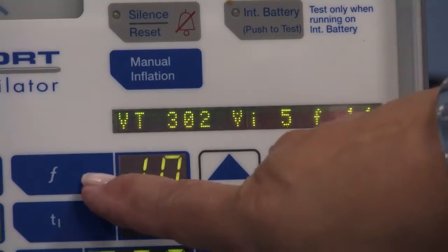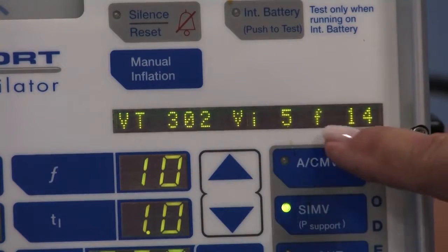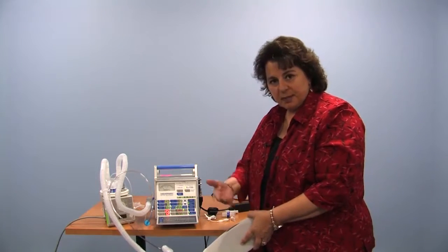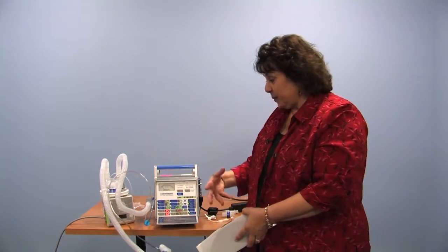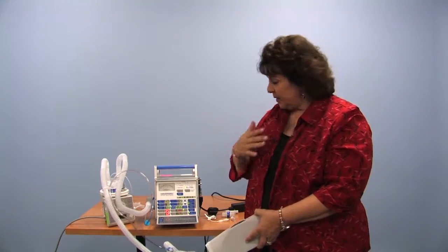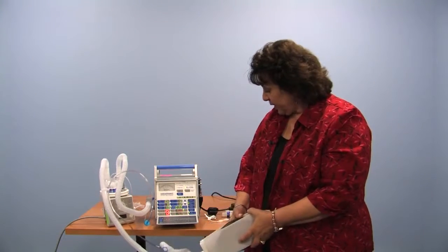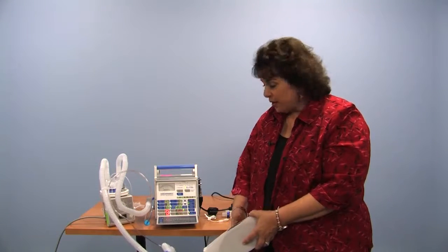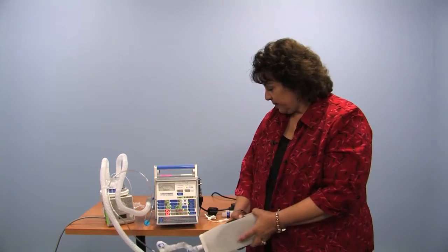And F, remember F is 10 breaths per minute. F is 14. So that's counting how many breaths a minute your child is receiving from the machine. So 10 of them are those preset 300 cc's of air that has been determined to be the right amount for your child's body. They fire 10 times a minute. And in between those breaths, your child is taking some more breaths, and they're using the pressure support. So this is total respiratory rate.